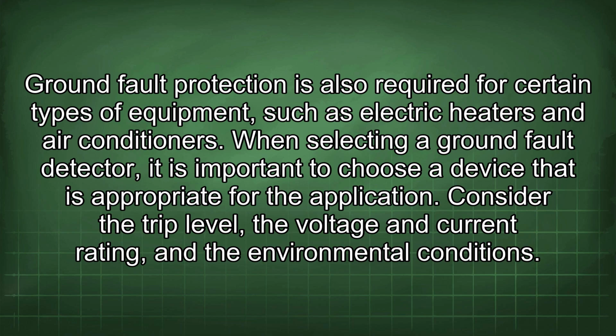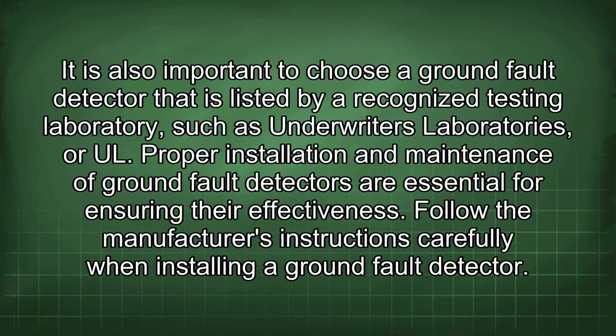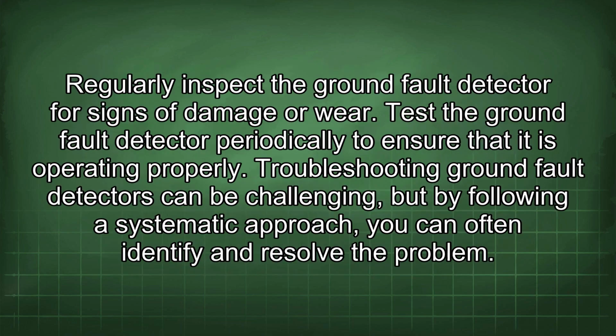When selecting a ground fault detector, it is important to choose a device that is appropriate for the application. Consider the trip level, the voltage and current rating, and the environmental conditions. It is also important to choose a ground fault detector that is listed by a recognized testing laboratory such as Underwriters Laboratories, or UL. Proper installation and maintenance of ground fault detectors are essential for ensuring their effectiveness. Follow the manufacturer's instructions carefully when installing a ground fault detector. Regularly inspect the ground fault detector for signs of damage or wear. Test the ground fault detector periodically to ensure that it is operating properly.